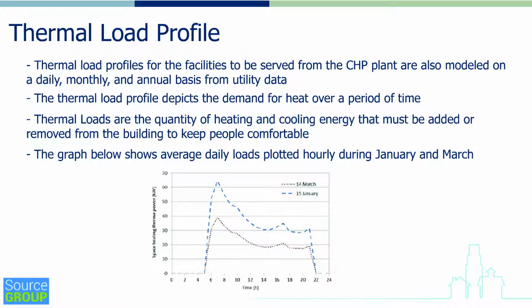Thermal load profile. The thermal load profiles for the facilities to be served from the combined heat and power plant are also modeled on a daily, monthly, and annual basis from utility data. The utility data being, in most cases, a gas meter. If the buildings run on oil, then it would be meter readings during the course of the day that would indicate what the load profile is.